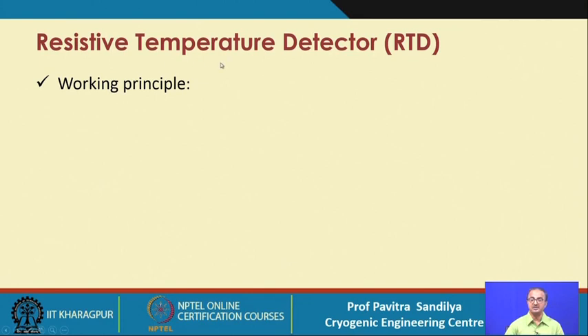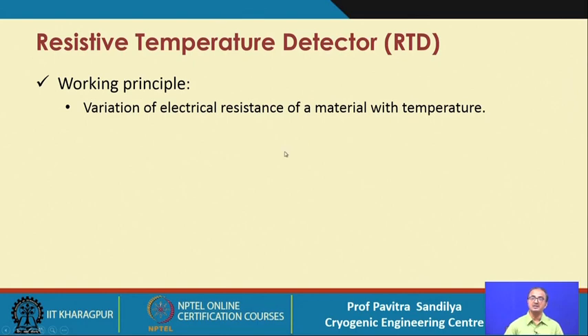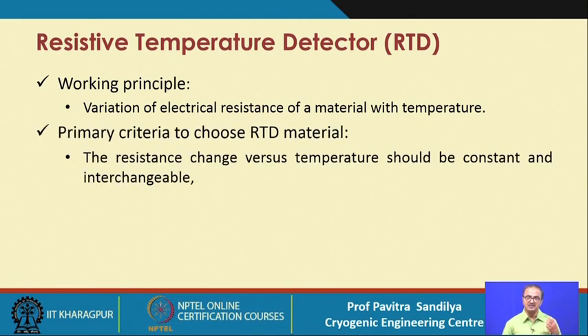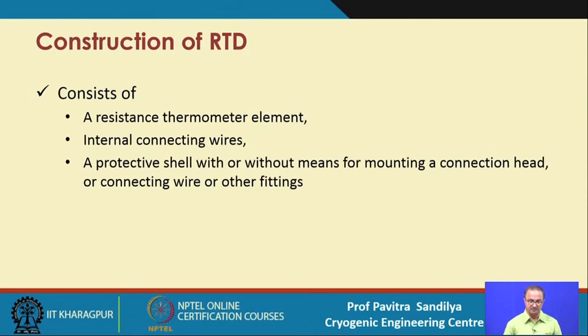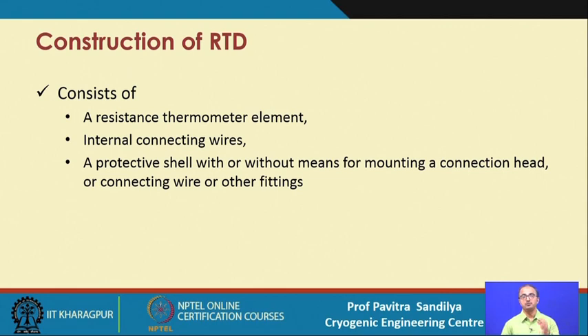The resistive temperature detector (RTD) works on the principle that the resistance of a material changes with temperature. Not all materials are suitable for RTDs — the sensitivity must be sufficient, meaning resistance change versus temperature should be constant and interchangeable, and the temperature coefficient should be large so it responds quickly to temperature changes. The RTD has a measuring element (resistance thermometer element) whose resistance changes with temperature, connected by wires and protected by a sheath.